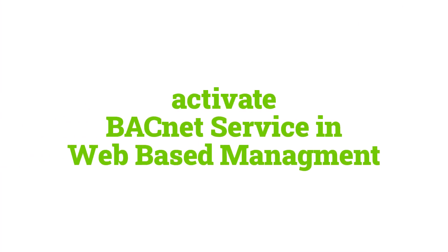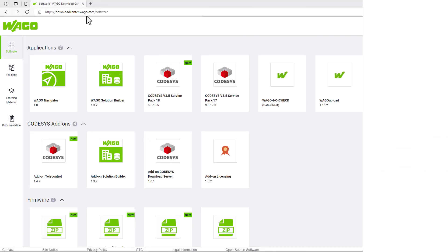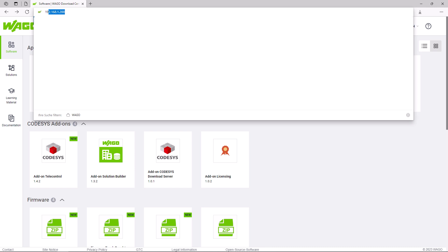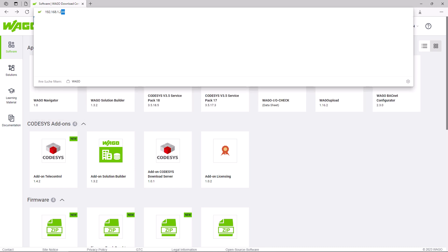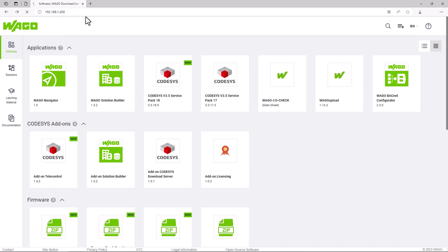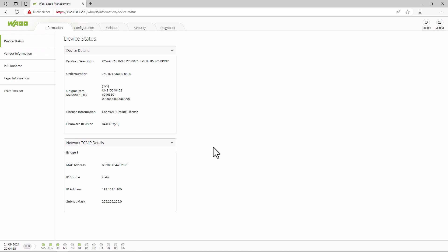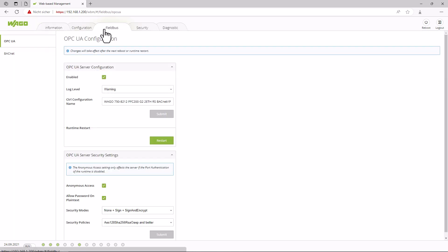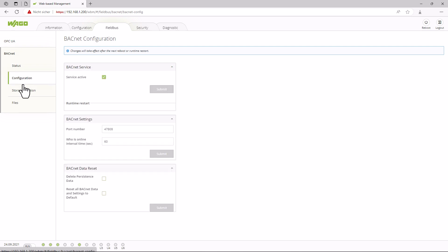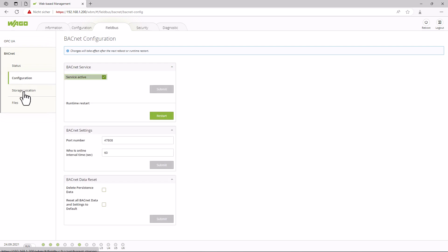When all components are ready for use, the first thing to do is usually to activate BACnet on the controller. This is done in the web-based management. We log into the web browser using the IP address and find the BACnet menu in the fieldbus tab, and enable the BACnet service under configuration. This is already enabled here as we are using a BACnet controller.